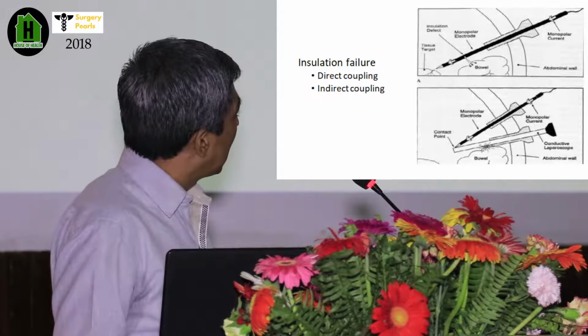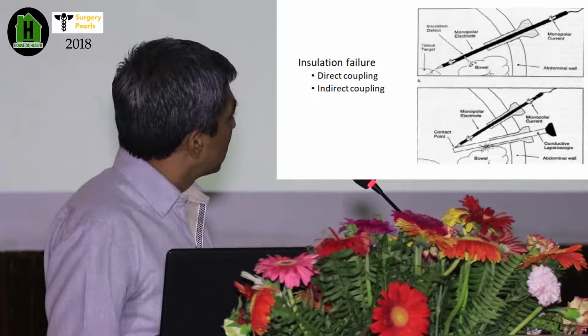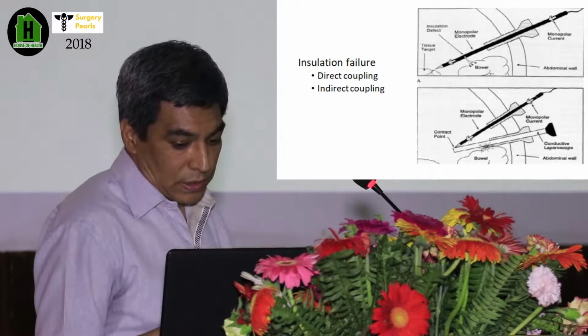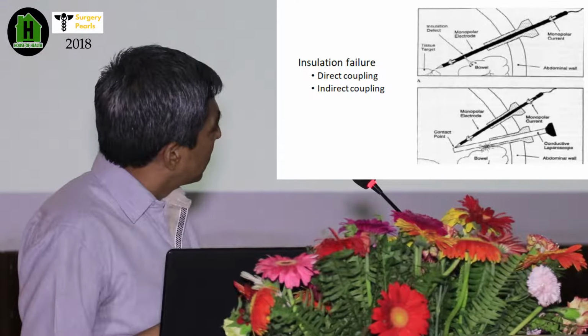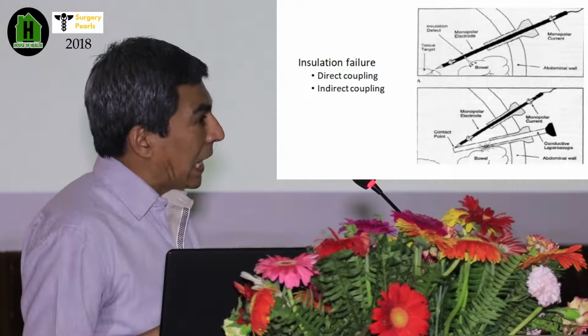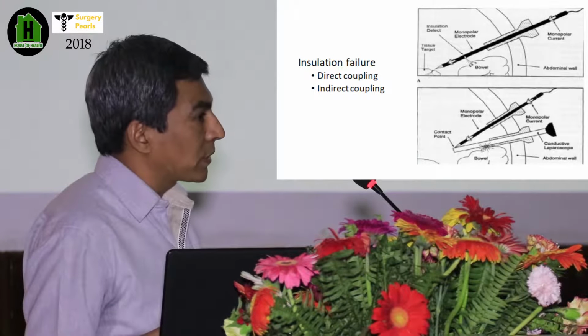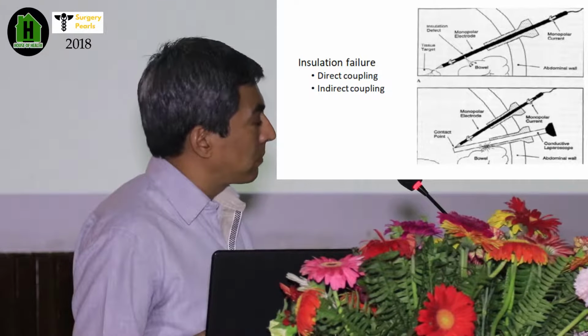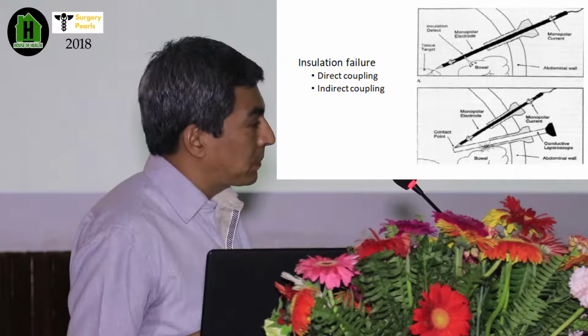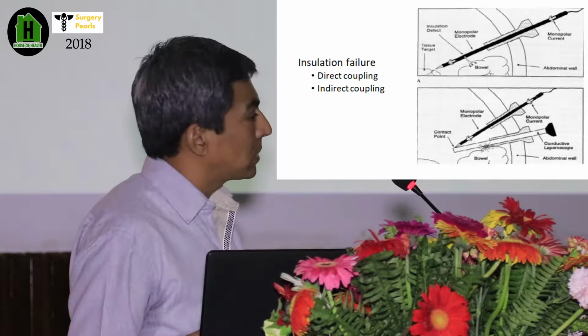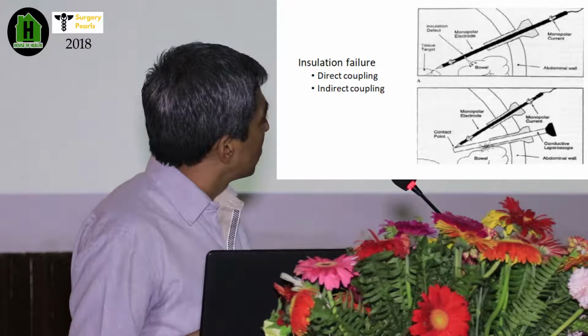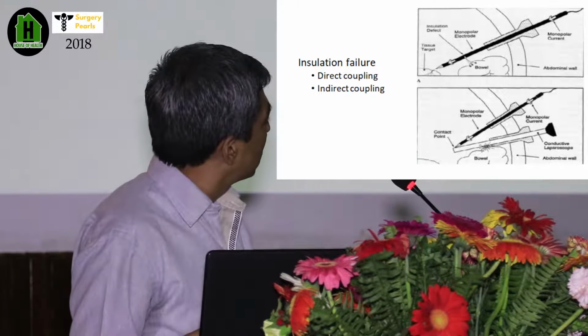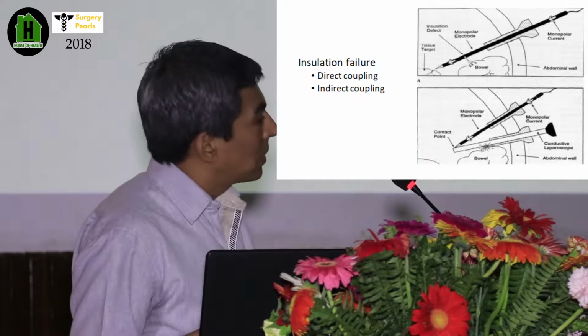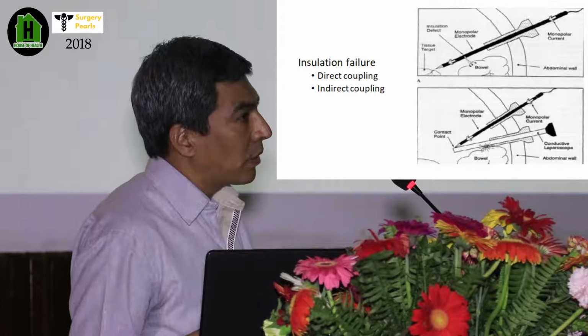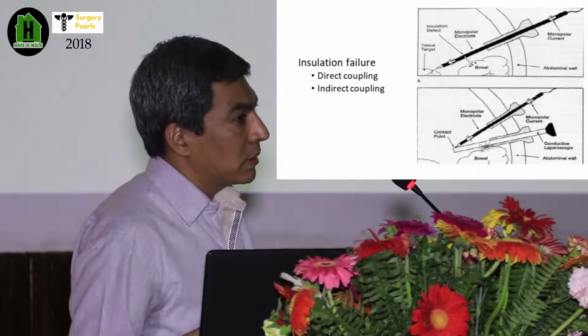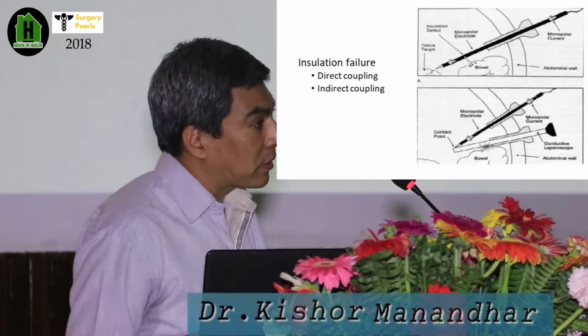Another one is indirect coupling. This is the laparoscopic instrument, and this is another instrument. There is no breach in the laparoscopic instrument here, but this other instrument is electrically active or a good conductor of electricity. Sometimes it is the cautery hook, sometimes the laparoscope itself, needle holders, aspiration needles, retractors. Those are the instruments we have to take care of. At the time of using those high energy devices, it might touch other devices. At the same time, it will have a deleterious effect on the other organs touching the unwanted instruments. So this is called the indirect coupling effect.